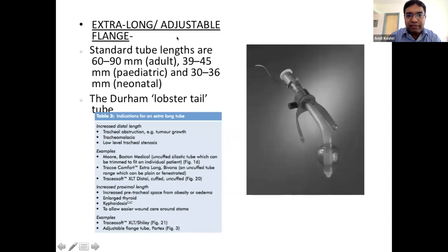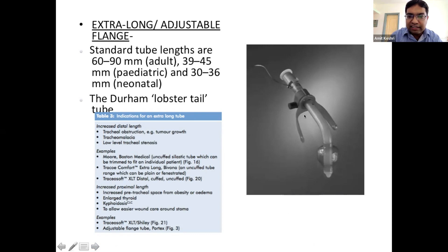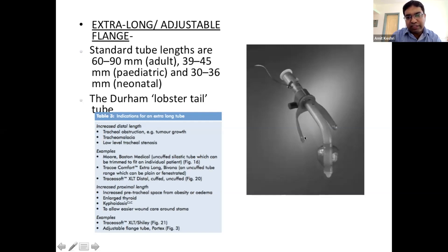Extra-long and adjustable flange tubes are important for obese patients — for example, a 120 kg patient — where the soft tissue is thick and the trachea dips sharply in a narrow neck. The flange position can be adjusted with a screw. These come as armoured and non-armoured variants and are used once or twice a year at PGIMER for very obese patients.